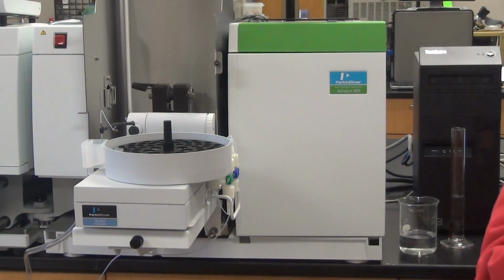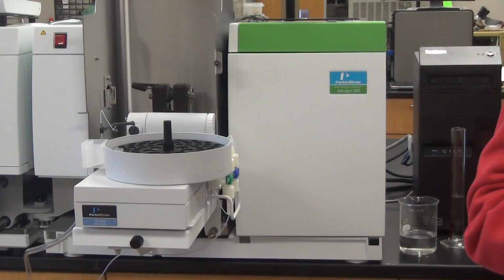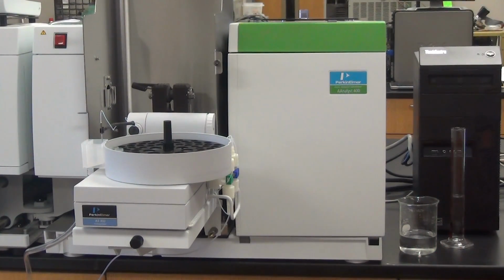Or I can hit analyze sample, but you still have to address where they are, and we haven't done that. It'd be just going to the method, right here, and I would say calibration, and I would say my blank, I want to call it this, standard 1, standard 2, standard 3. And there's the action, the AS location. That's where they would tell us. It automatically does it.